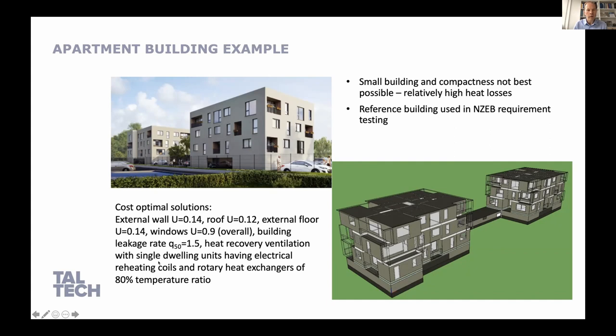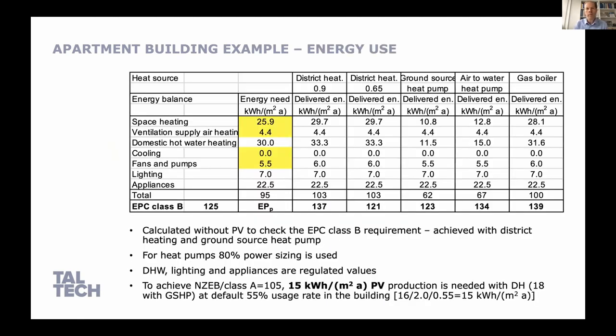Heat recovery ventilation, so there are single dwelling units, and these have electrical reheating coils and rotary heat exchangers, with 80% heat recovery efficiency. So the building is not compact, also a small part is heated. So there are quite a lot of heat losses in this case.